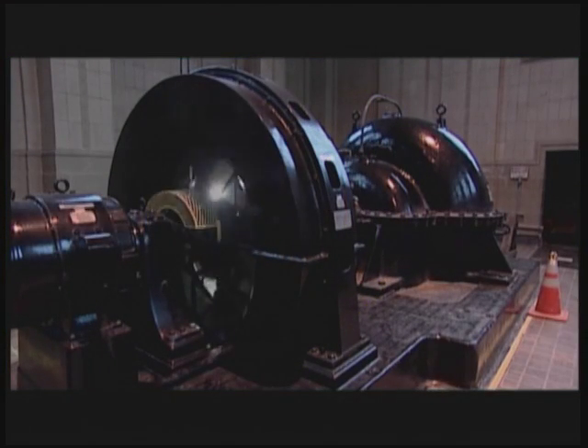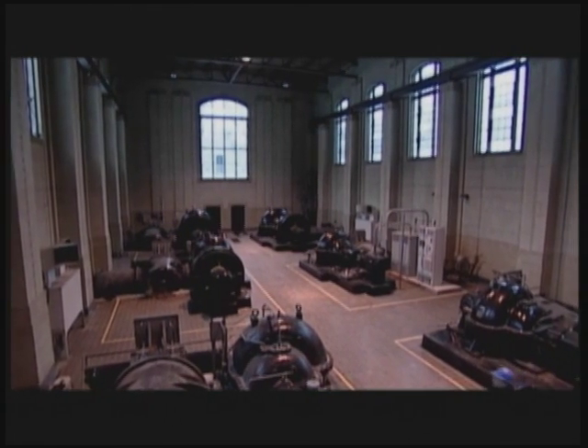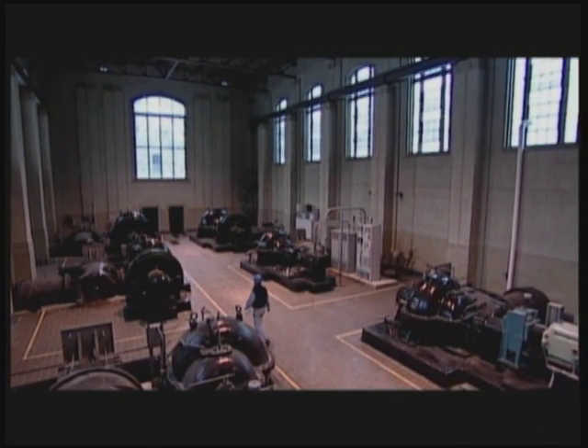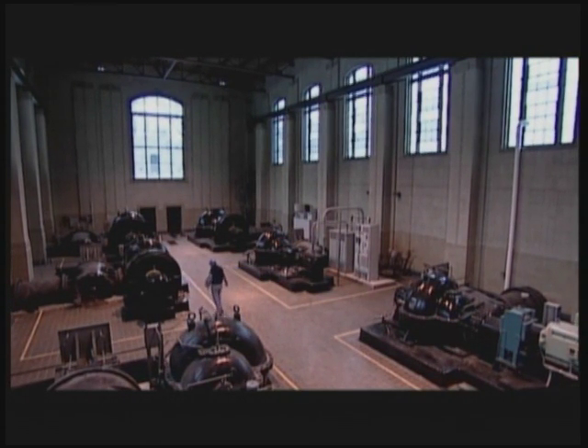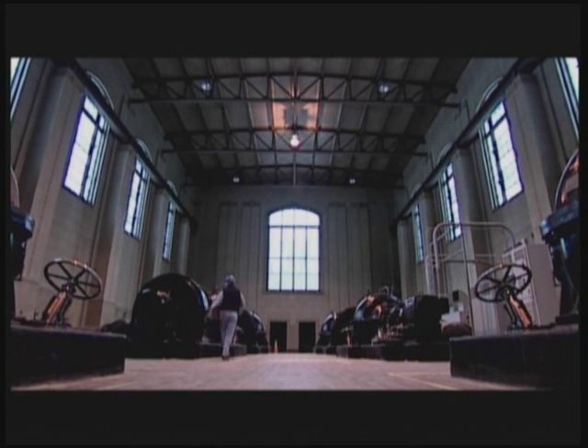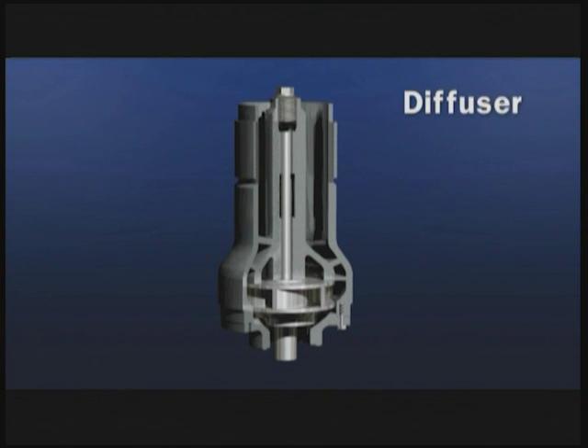Though there are numerous types and manufacturers of centrifugal pumps on the market, most are similar in construction and operation. Velocity pumps use a spinning impeller or propeller to accelerate water to high velocity within the pump casing. This is achieved in one of two different ways: in a volute or expanding spiral casing shape, or through diffuser vanes or channels such as those built into the bowls of vertical turbine pumps.